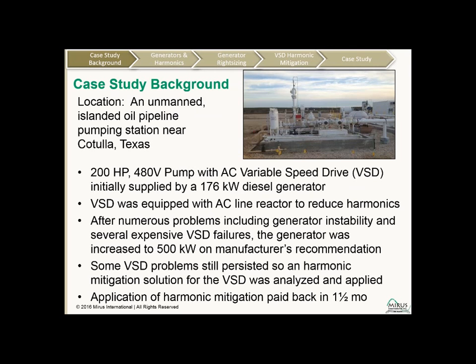The variable speed drive was equipped with an AC line reactor in an attempt to reduce harmonics, but that was not very effective, as it turned out. And after numerous problems, including generator instability and several expensive VFD failures, the generator was increased to a 500 kilowatt unit on the manufacturer's recommendation. Some problems persisted, and therefore harmonic mitigation was considered and eventually applied. With the application of the harmonic filter, there was a payback, as I mentioned earlier, of 1.5 months.